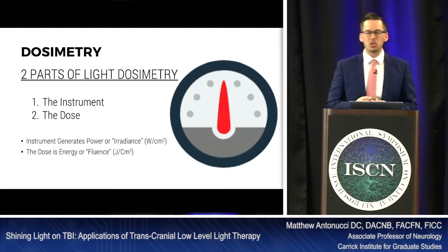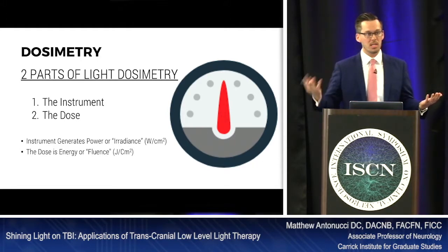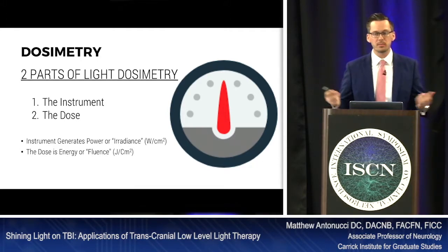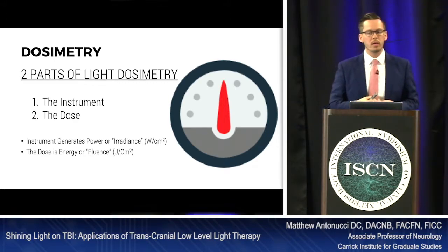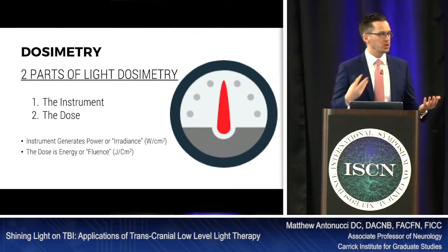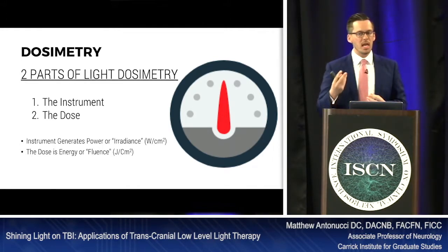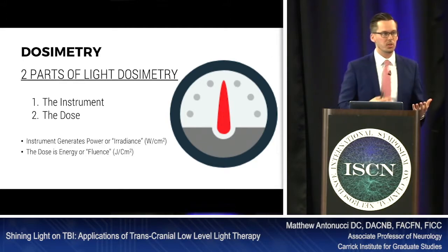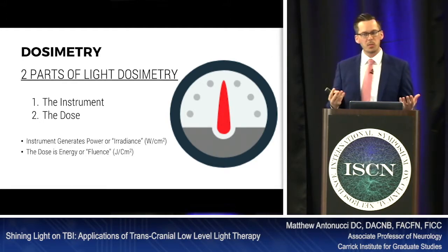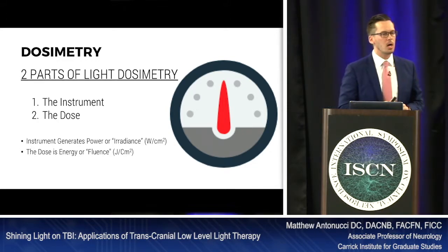There are two parts of dosimetry. The first is the instrument, and the second is the dose. The instrument generates power or irradiance, designated by watts per square centimeter. The dose is energy — also called fluence — which is joules per centimeter squared. So we're comparing watts per centimeter squared versus joules per centimeter squared, and we'll talk about the difference between irradiance and fluence.